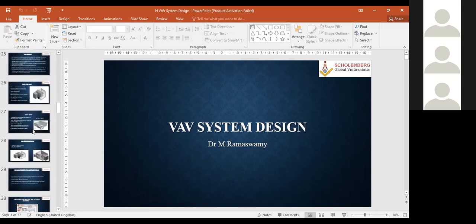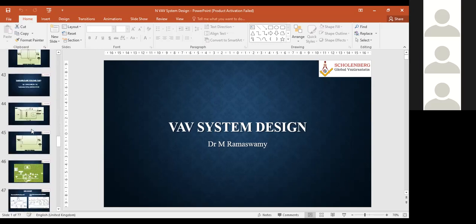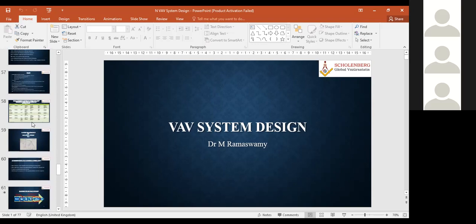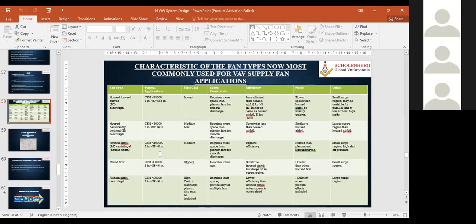I have given a comparative statement for the fan, forward curved versus backward inclined centrifugal. When majority of the time we go for this, the typical application is when CFM ranges from 25,000 to 70,000, and the first cost comes within medium and low. As for space constraints, it requires more space than plenum fans for smooth discharge, and efficiency is higher with the housed airfoil design. I have compiled this, and it will be useful, but as I told you, it all depends upon the air handling unit manufacturer and what type of air handling unit you select.